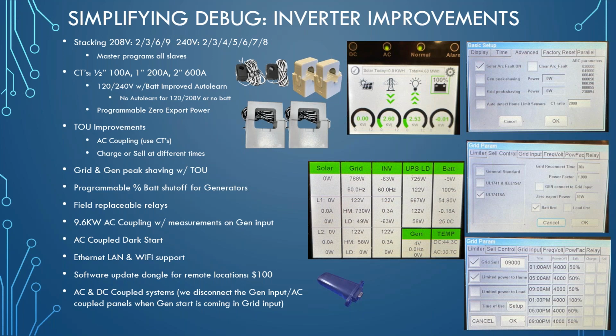And then two, very recently we introduced a software feature where, let me just back up a second here. In a world where you have AC coupled panels and a generator at the same time, you can't run them both at the same time, because we do something called frequency curtailment to control your AC coupled panels. They can't be on at the same time, because the generator would define the frequency and we wouldn't be able to tell them to stop making as much power, et cetera. You might be able to see how that could be a problem.